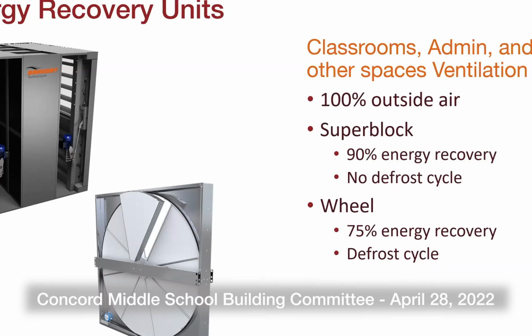And this often happens when it's really cold out, which means there's a large delta in temperature, like 10 degrees outside and 70 degrees in the building. So you're missing out on all that energy you could be recovering during that time. The superblock, since it isn't using wheel technology, doesn't have a spot for frost buildup, so it's able to eliminate that and is therefore able to claim more energy efficiency.